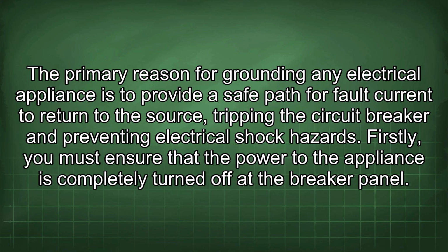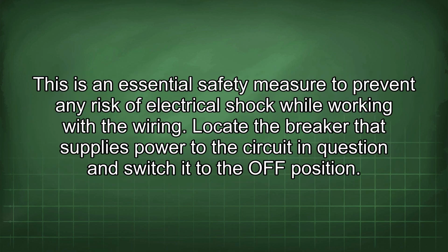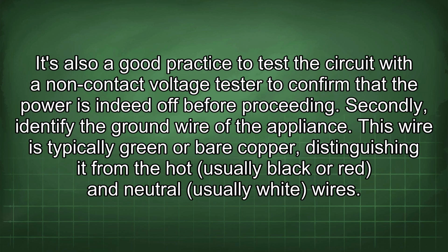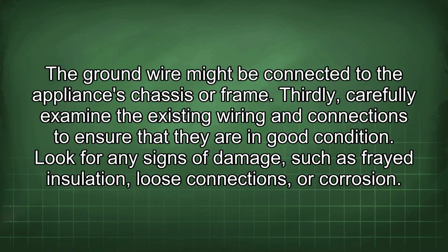Firstly, you must ensure that the power to the appliance is completely turned off at the breaker panel. This is an essential safety measure to prevent any risk of electrical shock while working with the wiring. Locate the breaker that supplies power to the circuit in question and switch it to the OFF position. It's also a good practice to test the circuit with a non-contact voltage tester to confirm that the power is indeed off before proceeding. Secondly, identify the ground wire of the appliance. This wire is typically green or bare copper, distinguishing it from the hot, usually black or red, and neutral, usually white, wires. The ground wire might be connected to the appliance's chassis or frame.